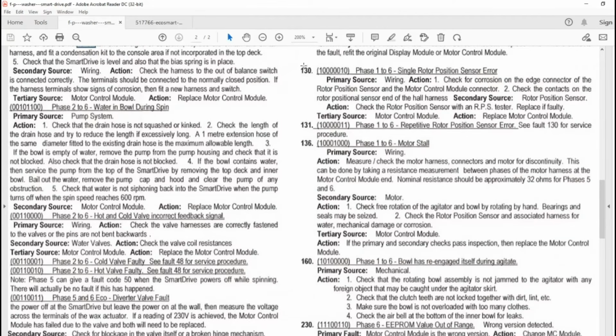Fault 130. So 130 and 131, and also 136. These two mean the rotor position sensor, the sensor on the motor, is not giving a correct signal. Usually corrosion. So 130 is the one you'll start getting to start with, and then as it gets worse and worse, you'll get the 131, and then the machine just refuses to go. 136 is the motor stall. Now this is usually, if you haven't already done work on the machine, a faulty RPS. So if the rotor position sensor is saying that the motor is not turning, or not turning the direction it's expecting, then you'll get this 136 rather than a 130 or 131.